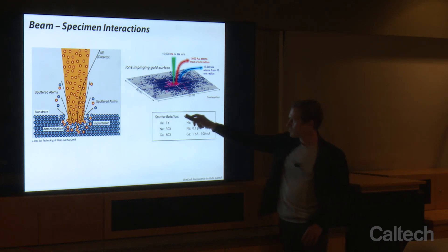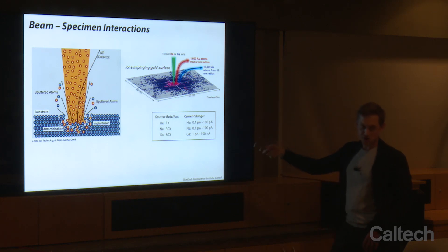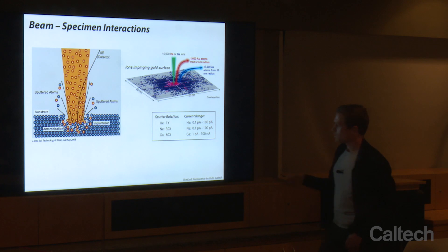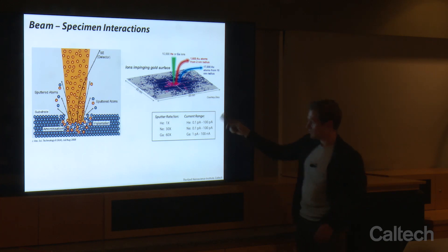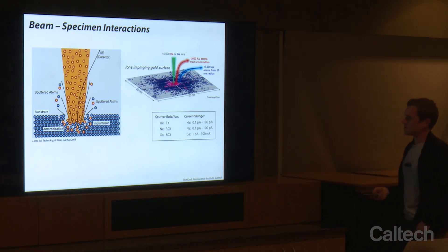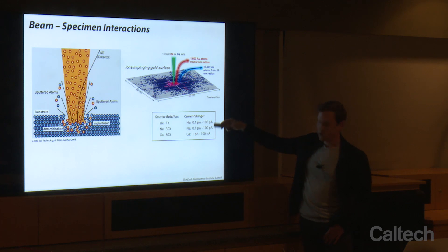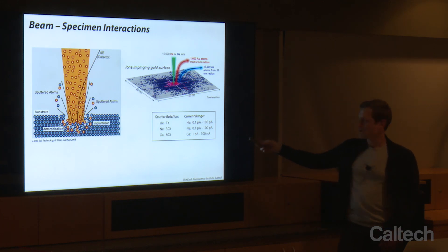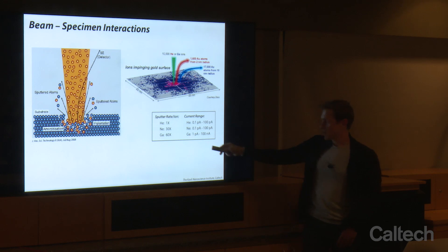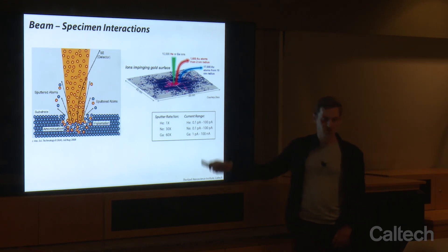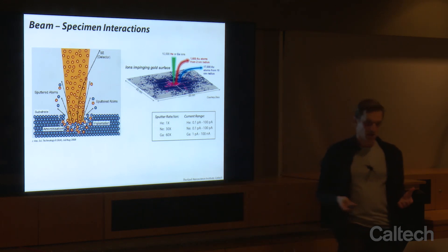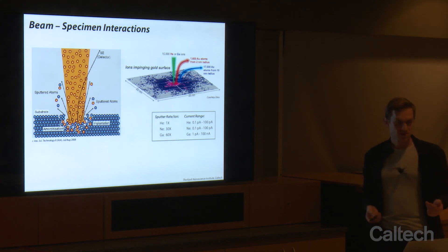The sputter rate is very different across ion species. If helium has a sputter rate of 1x, neon is about 30x, and gallium about 60x per unit current. The current ranges available are also very different: gallium can operate as high as 100 nanoamps, whereas helium and neon operate at only about 100 picoamps at the highest. When you combine the higher sputter rate and higher current range, you get orders of magnitude larger volume removal using a gallium technique relative to the other techniques.